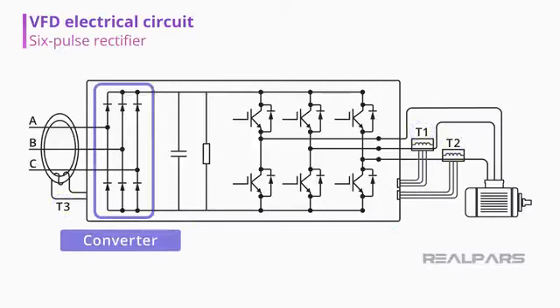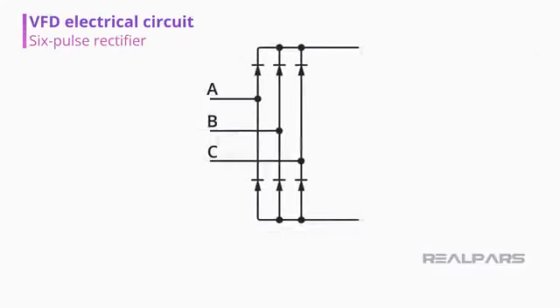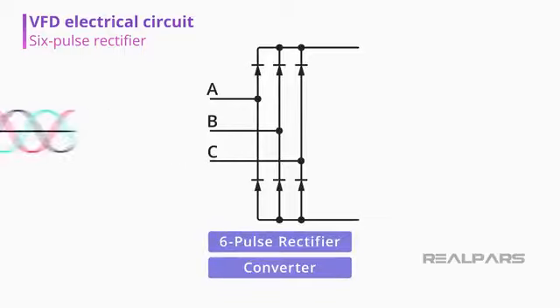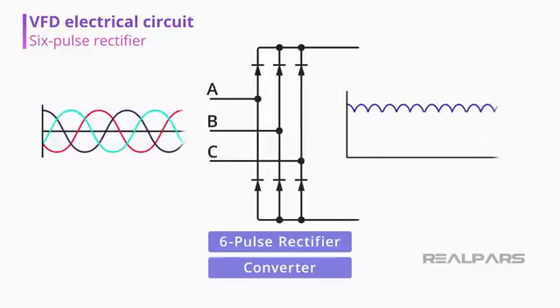Following, we have the Converter, also called a Rectifier. If we were to expand and look at the Rectifier Diagram, this is what it would look like. This is called a 6-Pulse Rectifier or Converter, and it's where the 3-phase alternating current gets converted into direct current by the use of diodes.